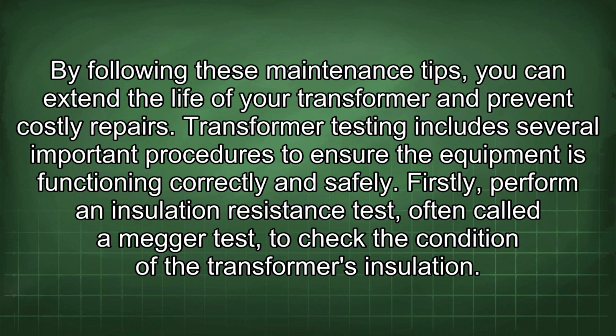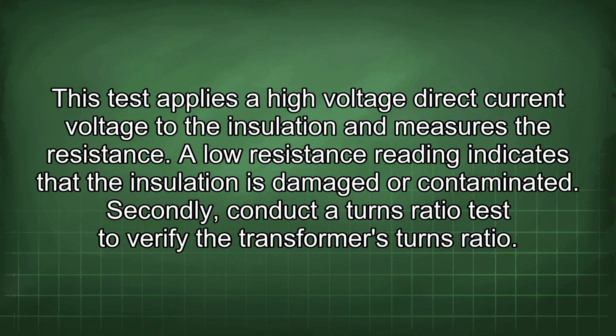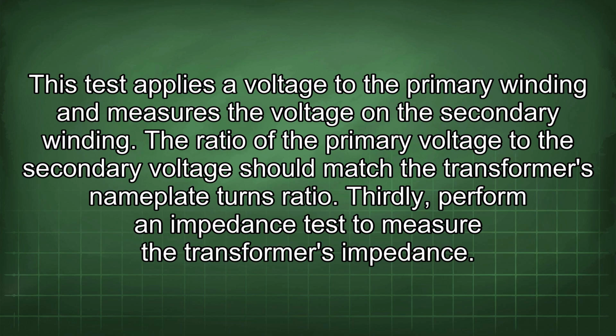Transformer testing includes several important procedures to ensure the equipment is functioning correctly and safely. Firstly, perform an insulation resistance test, often called a megger test, to check the condition of the transformer's insulation. This test applies a high voltage direct current voltage to the insulation and measures the resistance. A low resistance reading indicates that the insulation is damaged or contaminated. Secondly, conduct a turns ratio test to verify the transformer's turns ratio. This test applies a voltage to the primary winding and measures the voltage on the secondary winding. The ratio of the primary voltage to the secondary voltage should match the transformer's nameplate turns ratio.